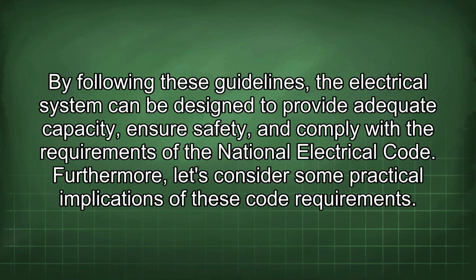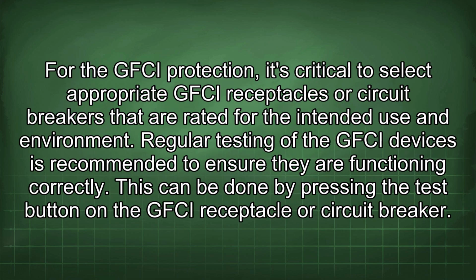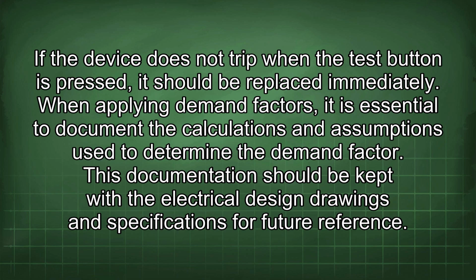Furthermore, let's consider some practical implications of these code requirements. For the GFCI protection, it's critical to select appropriate GFCI receptacles or circuit breakers that are rated for the intended use and environment. Regular testing of the GFCI devices is recommended to ensure they are functioning correctly. This can be done by pressing the test button on the GFCI receptacle or circuit breaker. If the device does not trip when the test button is pressed, it should be replaced immediately.